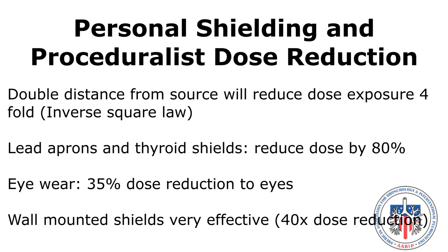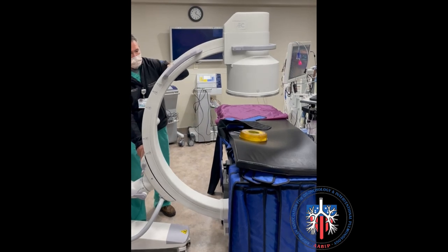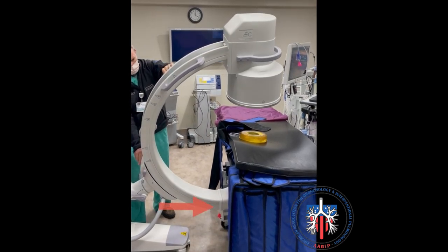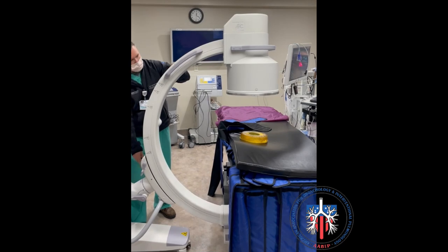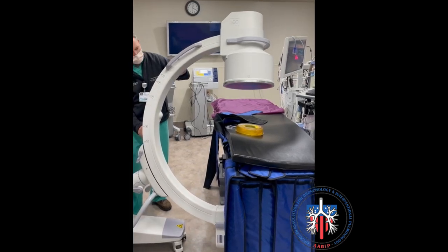Personal shielding and proceduralist dose reduction: doubling the distance from the source will reduce dose exposure by four-fold. Lead aprons and thyroid shields will reduce dose by 80%. Eyewear will reduce dose by 35% to the eyes. Wall-mounted shields are very effective and will reduce dose by 40 times. This is an example of angling the C-arm with the x-ray tube angled cephalad and then caudad.